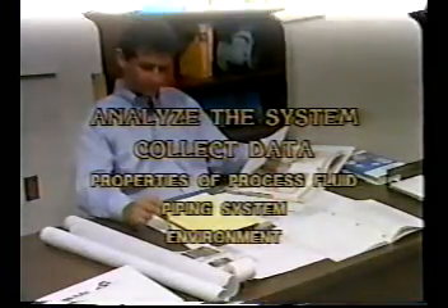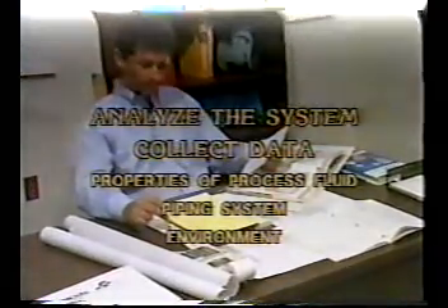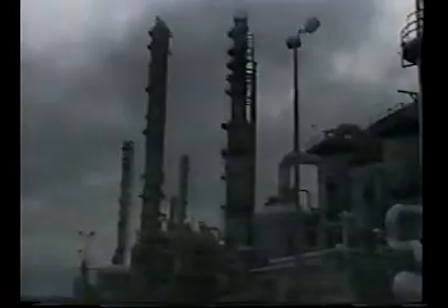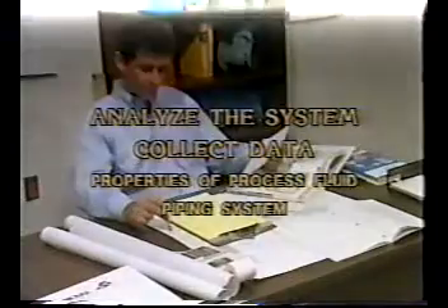The environment where the valve will be installed can also have an impact on valve selection. As you may recall, the classification of the area for electrical hazards is one important factor when making a selection. Other factors include climatic conditions, such as temperature extremes, atmospheric contamination, such as corrosive dusts and vapors, the seismic zone classification, and any unusual plant procedures, such as washdown or decontamination.